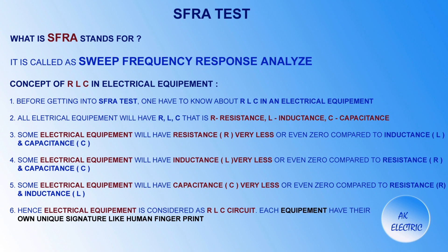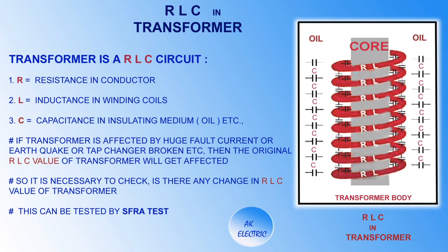Each equipment has its own unique signature, like a human fingerprint. Inside a transformer body, one can observe resistance in the conductor, inductance in the winding coils, and capacitance in the insulating medium — that is, transformer oil. If a transformer is affected by a huge fault current, earthquake, or tap changer breakage, the original RLC values of the transformer will get affected. So it is necessary to check for any change in RLC values, and this can be tested by the SFRA test.